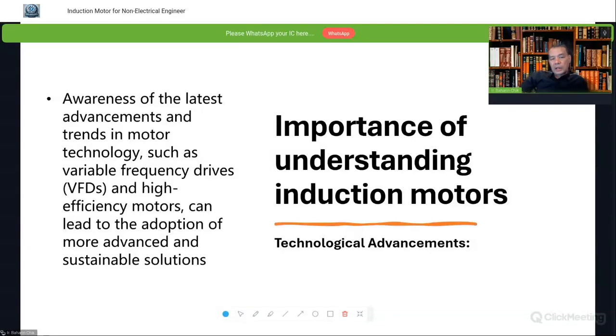The next importance of understanding induction motors is understanding the various ways in which they can be controlled and started. Having understood this, we can employ more advanced solutions and give a wider operating range for the driven equipment to operate. For example, direct online motors compared with VFDs. VFDs will give you a wider operation range in terms of process. But the direct online starter will give you a fixed speed, and then there is no way you can control the flow or the pressure of the compressors or pumps. So understanding of this induction motor is important in terms of controlling the plant.